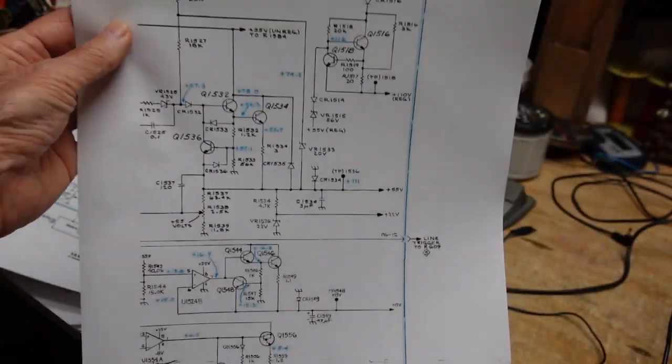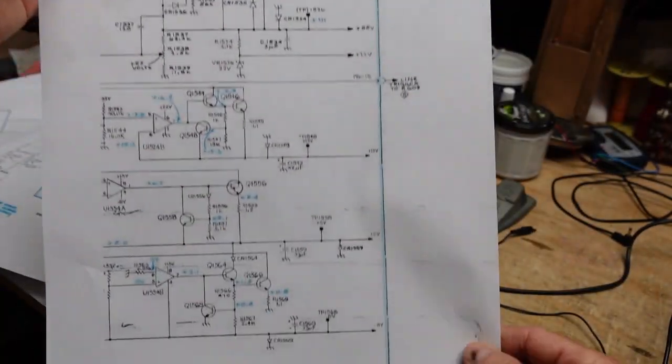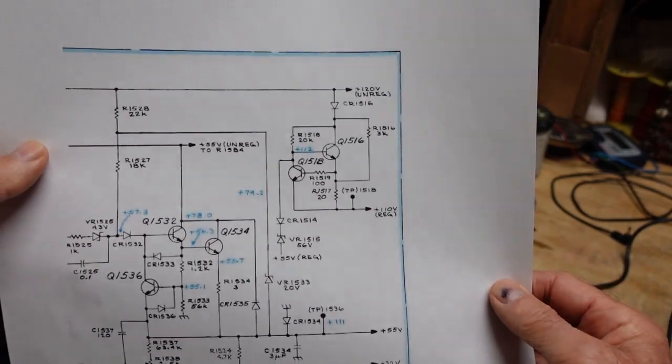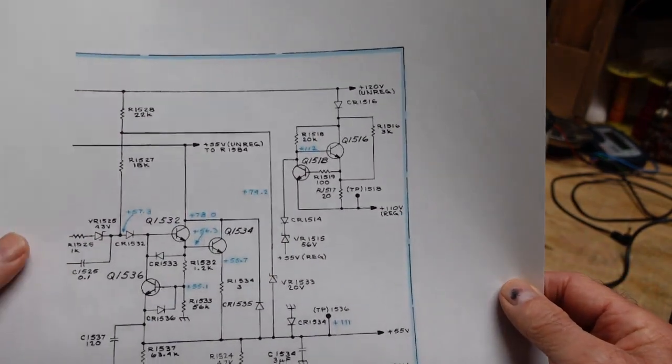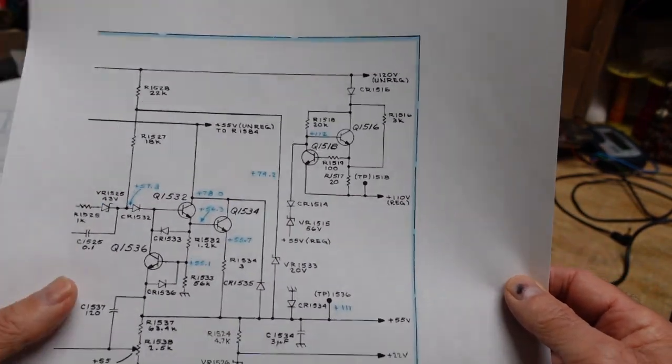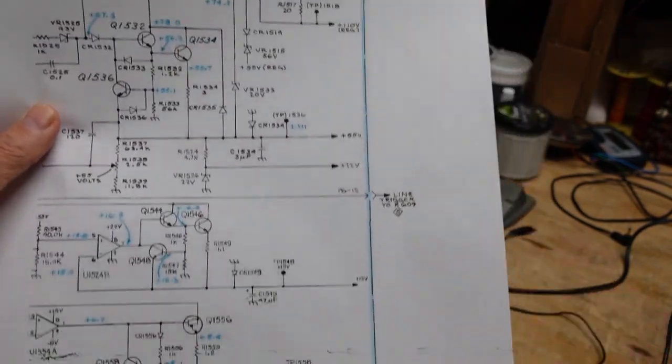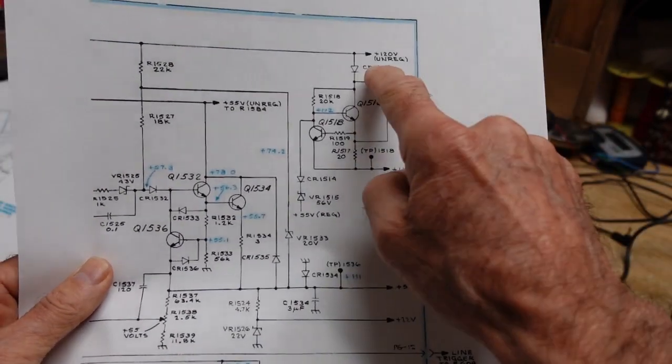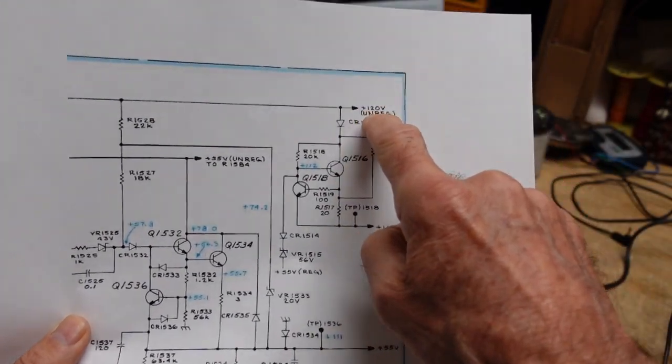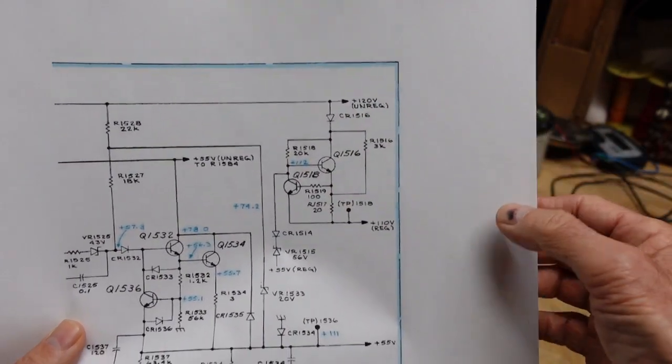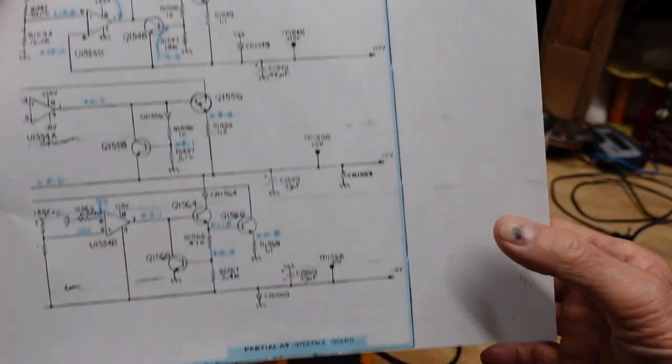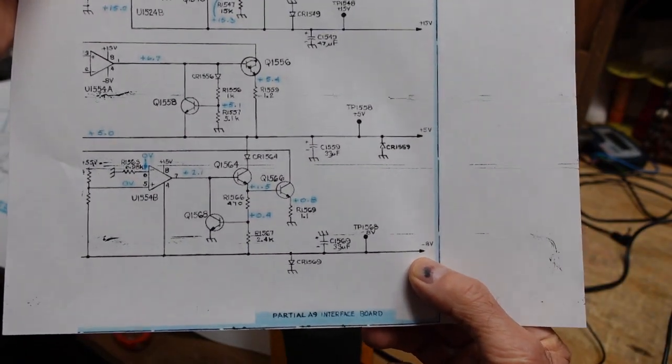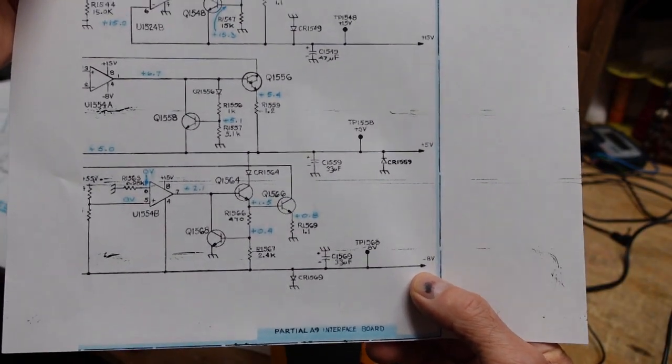So I want to go through the low voltage power supplies and see if we had a problem there. As you can see, there's quite a bit to this and this is just a partial of the schematic, but it gives all the expected output voltages from a positive 120 volt unregulated all the way down to a negative 8 volt.